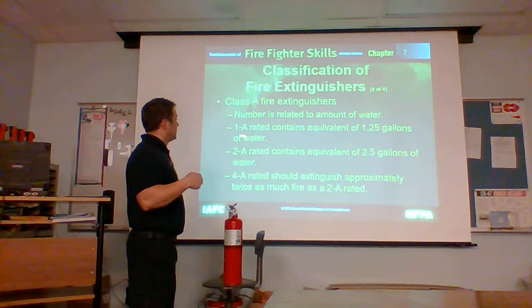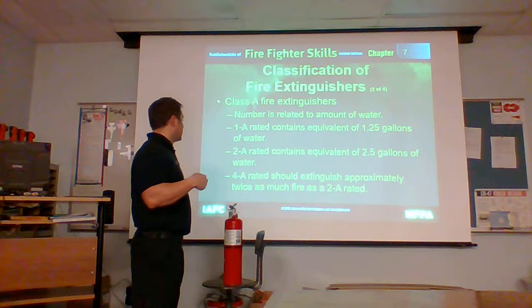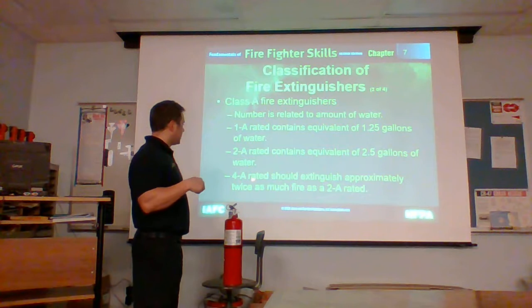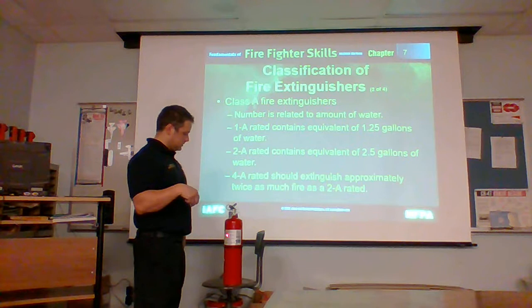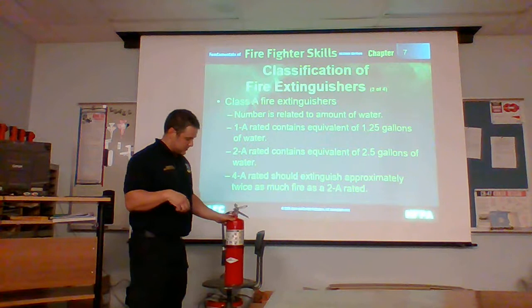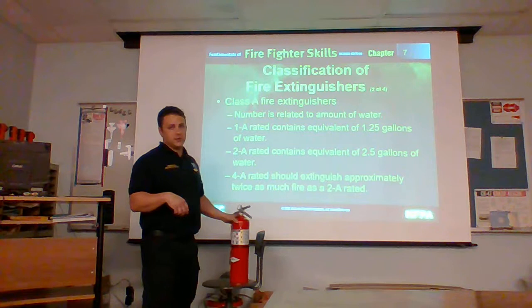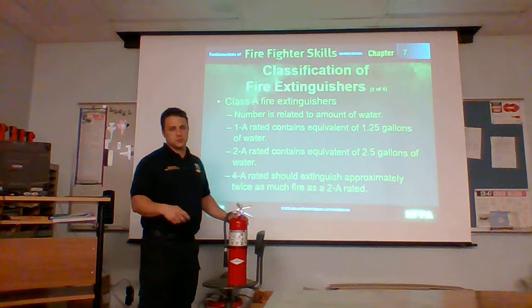A 1A rating contains the equivalent of 1.25 gallons of water. 2A contains the equivalent of 2.5 gallons of water. The 4A contains approximately twice as much as the 2A, so this would be about the equivalent of 5 gallons of water. But this is in a 10-pound extinguisher, and 5 gallons of water would be around 40 pounds — a whole lot easier to carry this than 40 pounds of water.